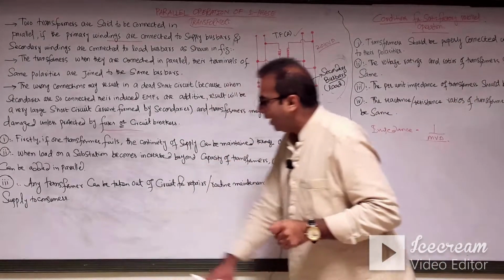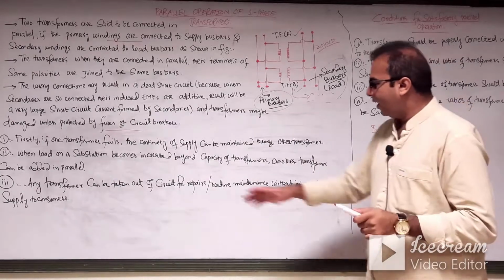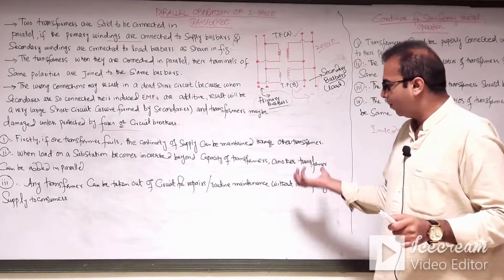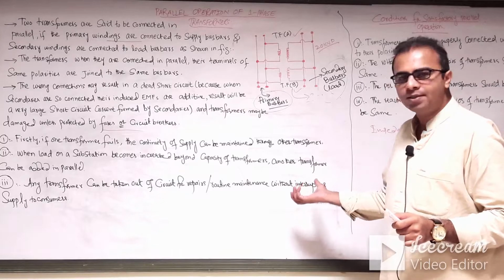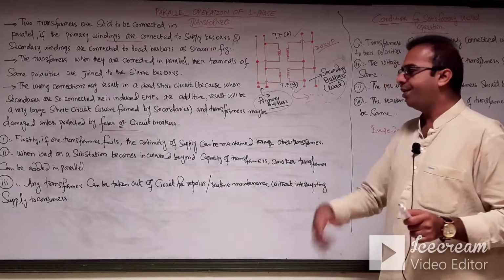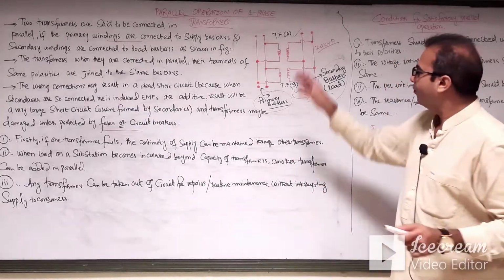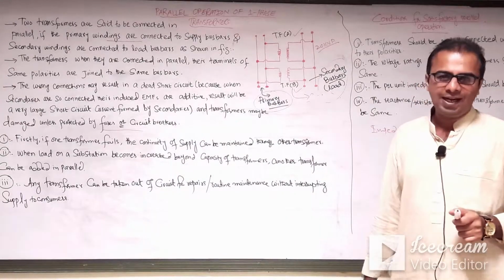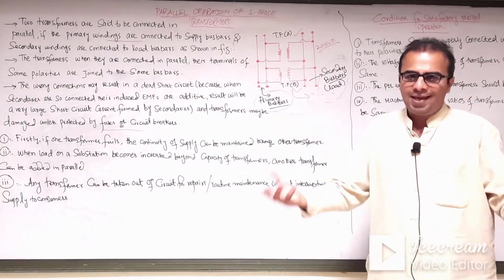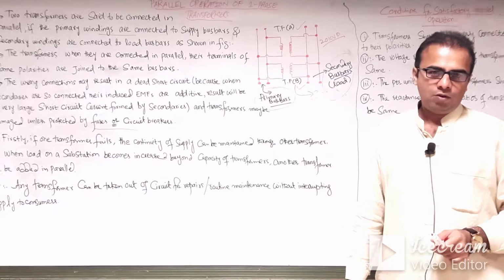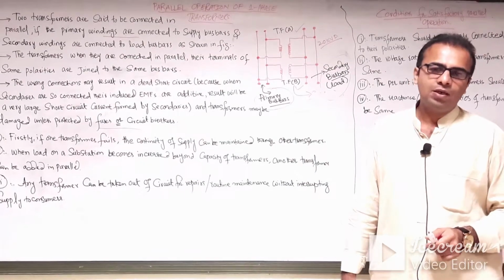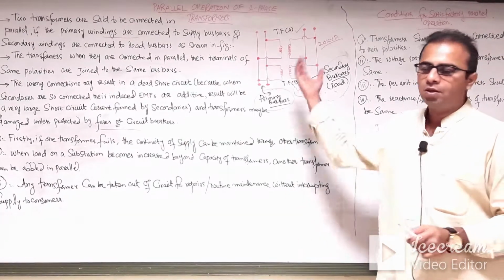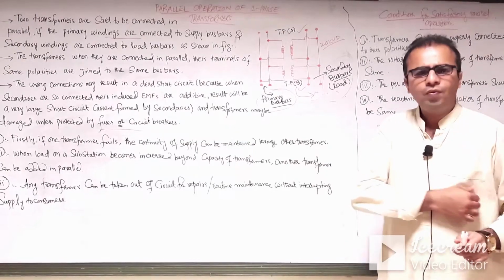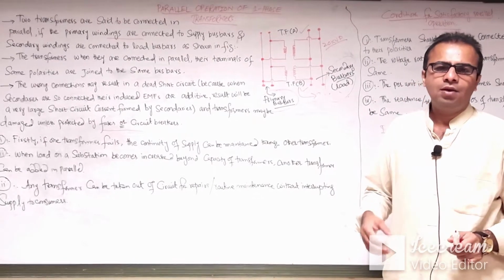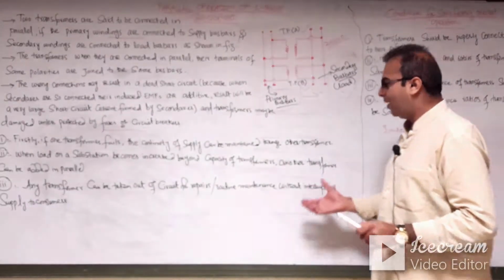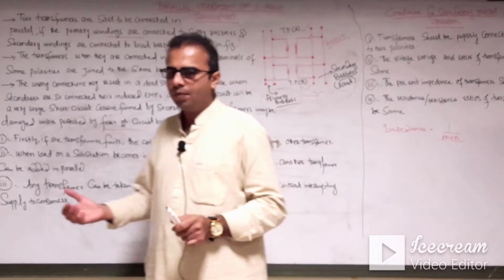Number three, any transformer can be taken out for circuit repairs or routine maintenance without interrupting supply to the consumer. If transformer A is shut down for any reason, or if we have to do repair work or routine maintenance on transformer A, we can easily do the repair work and maintain the supply from transformer B.